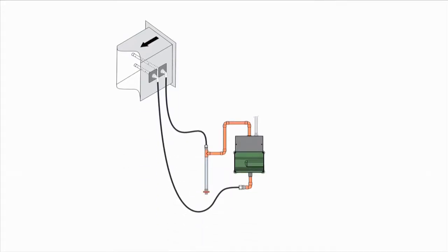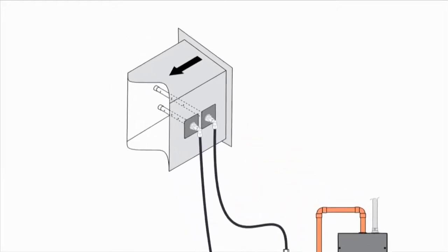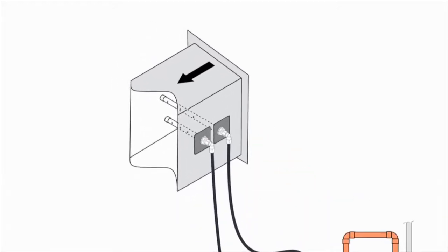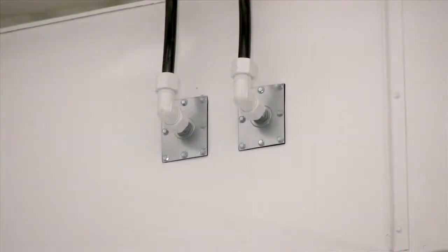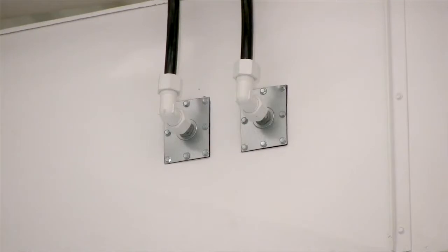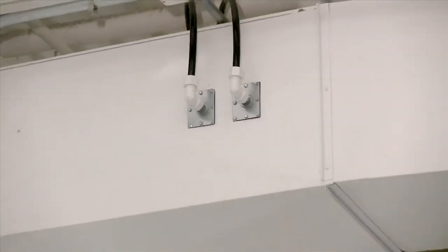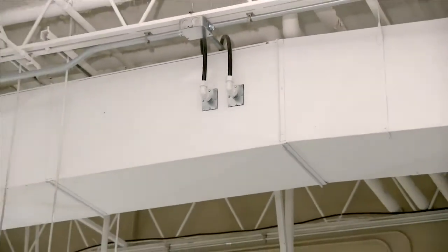This diagram shows a typical XAD installation. Like a traditional duct detector, the XAD sampling and exhaust tubes are installed in the duct. One thing to notice here is that with XAD, the tubes are on separate plates, making it easier to reuse existing holes in a retrofit installation.